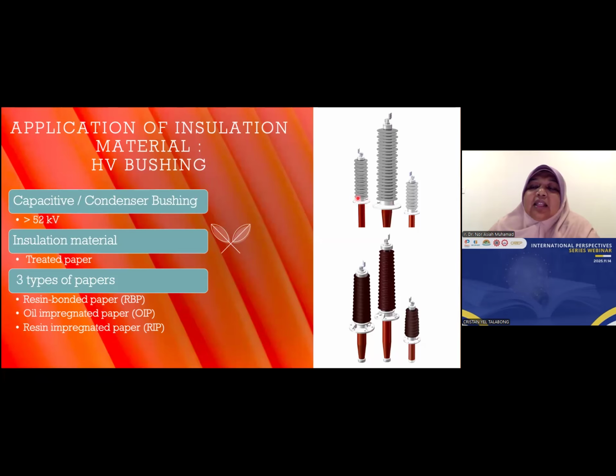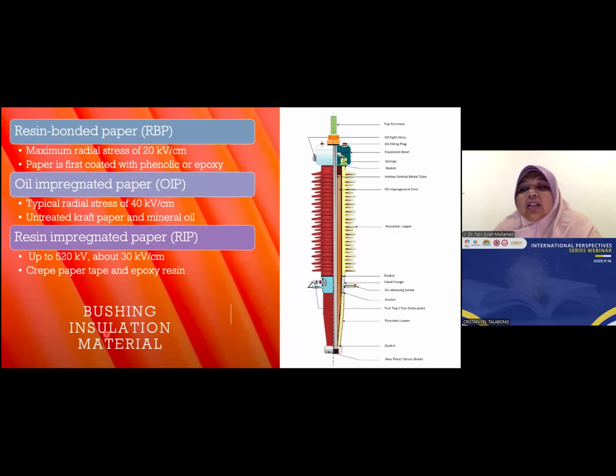So the next is the bushing. Bushing is the connector between the transmission line and the equipment. For bushing, we have capacitive and condenser bushing. The operation is above 50 kV. The insulation materials are treated paper. There are three types of treated paper: resin bond paper, oil impregnated paper, and resin impregnated paper. So where is the paper here? This is the conductor from the incoming to the outgoing, or from the line to the equipment.